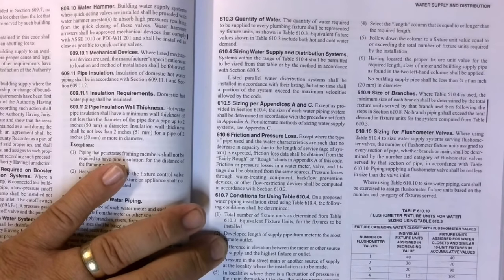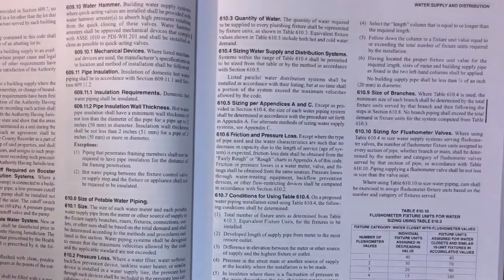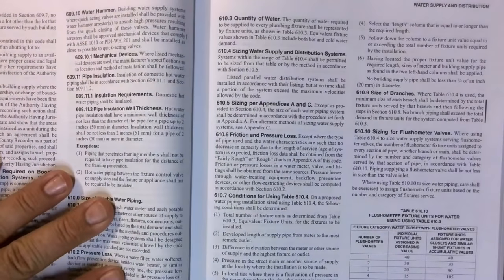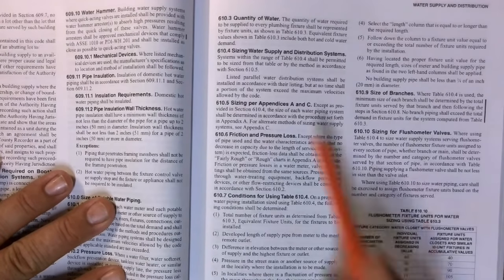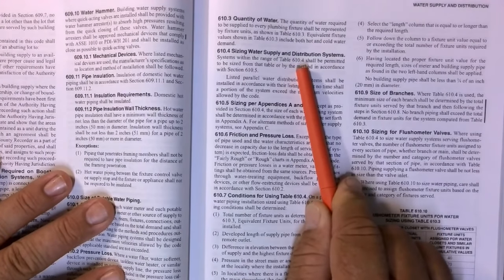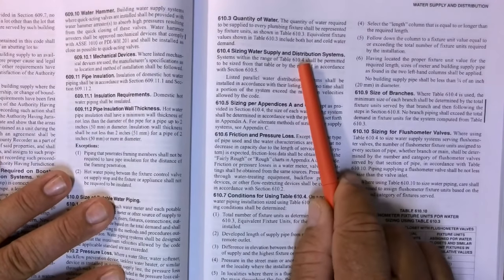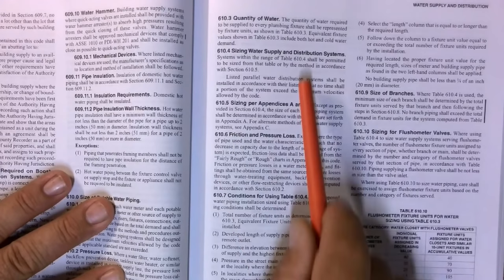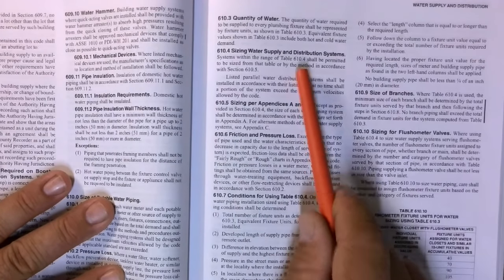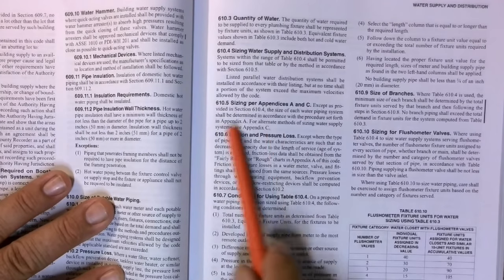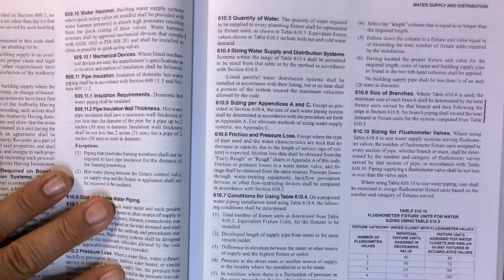Section 610.5, we do that in plumbing 3, and that's in Appendix A. It is all based on flow restriction, distance, elevation, and pressure loss. So it's more of an engineered method than what is provided here. Just so you know, table 610.4, which is where we get all of our sizing calculations, all the numbers on that table are derived from this sizing situation where we use Appendix A.